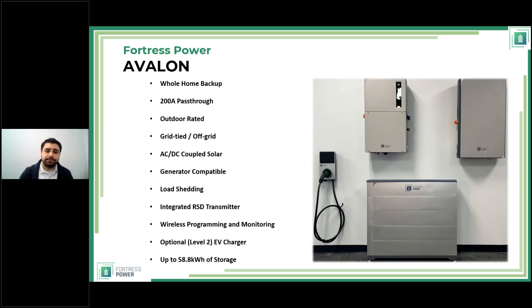I want to switch focus to the innovation — the Avalon system, rather than existing products. The Avalon can do whole-home backup with 200-amp passthrough; it works with AC-coupled or DC-coupled solar; it is generator compatible; it can be installed outdoors; it has an integrated rapid shutdown device transmitter — you can request either APsmart or Tigo transmitter when ordering.